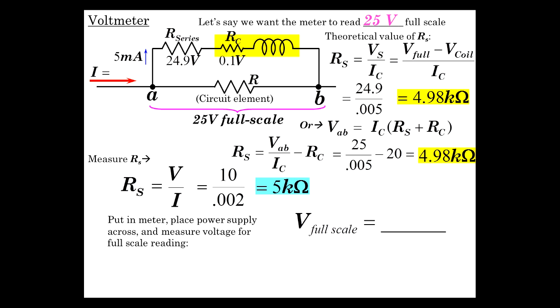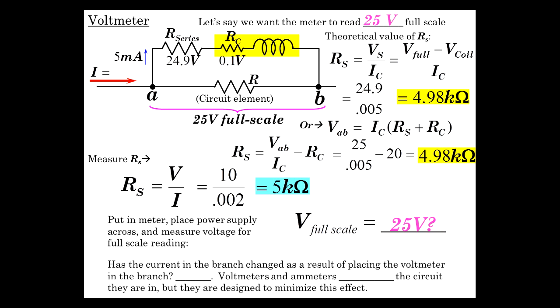So you use that, you stick the 5k ohm resistor in there, you put it in the meter, you put the power supply across the circuit, you measure the voltage with an external voltmeter. You measure the voltage across here, then when this is full scale, when the meter reads full scale, and hopefully that voltage will be about 25 volts. There'll be some variance with that because the series resistors aren't going to be perfect.